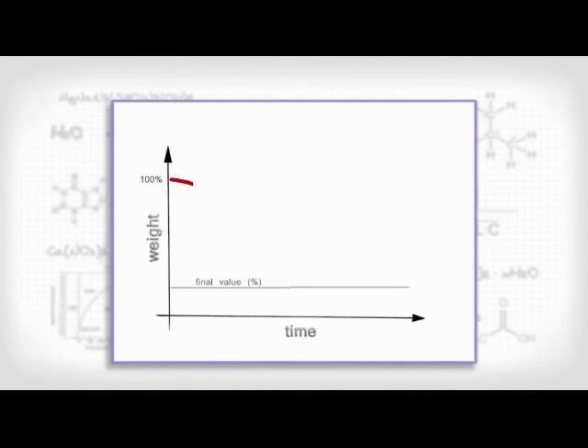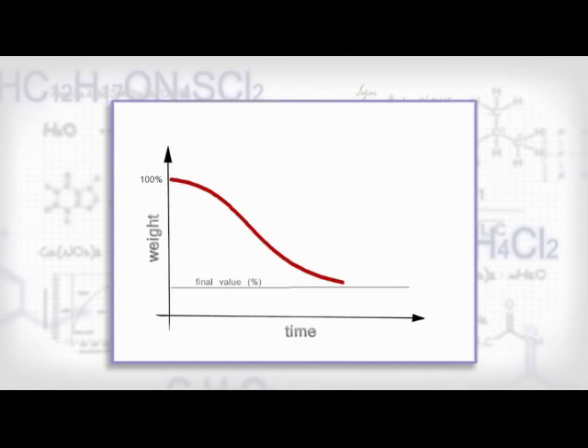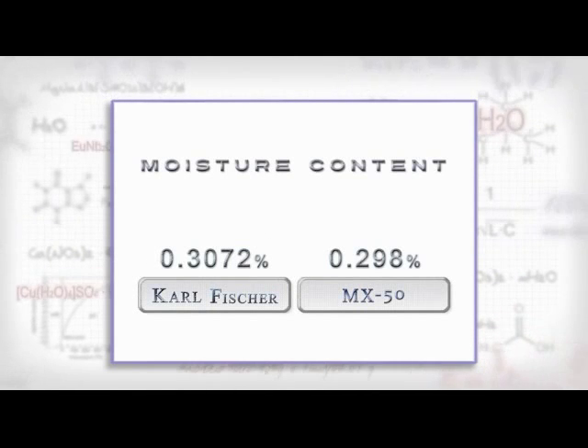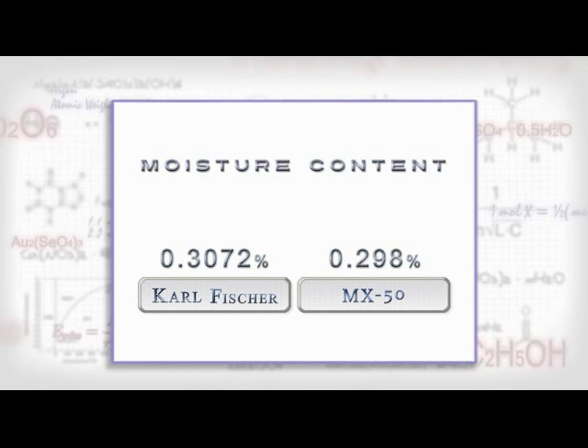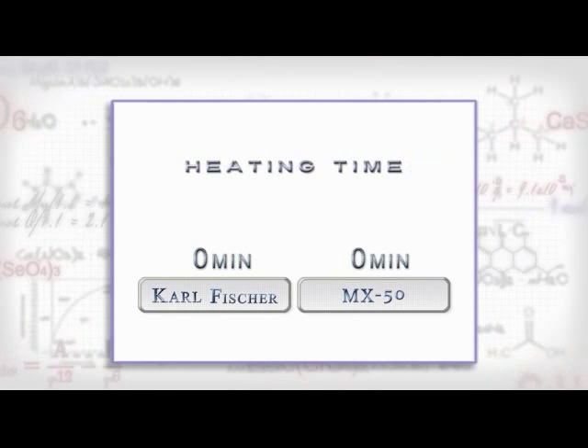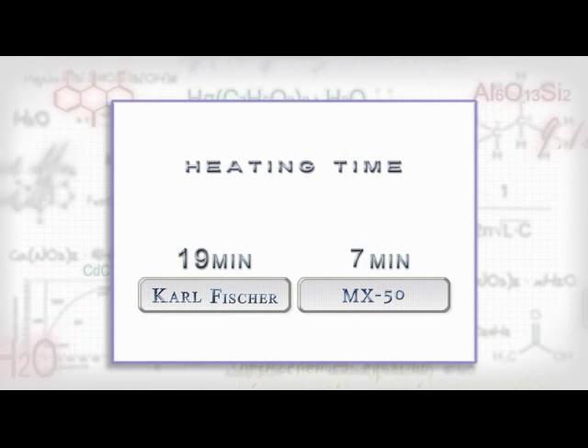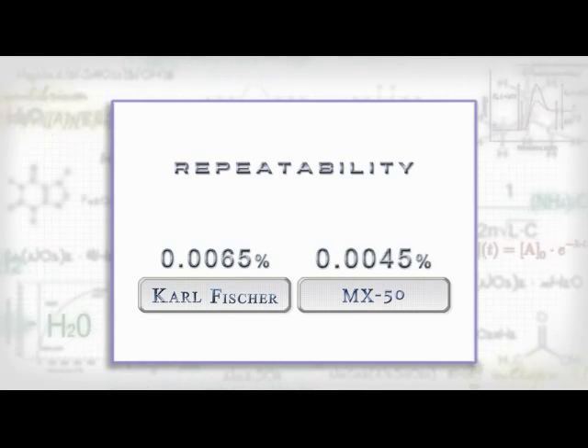A&D analyzers use the thermogravimetric or loss on drying principle and offer the accuracy of the Karl Fischer technique but in less time and with better repeatability.